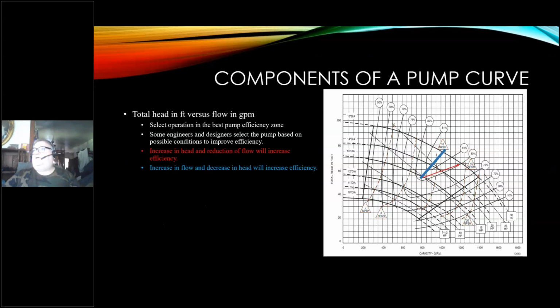All right, total head. Let's talk about how these interact. Total head in feet versus flow. Okay, this is the resistance. Select the operation of the best pump efficiency zone. So that blue line kind of tells us this is the straight line where we might get the best efficiency. Some engineers and designers select the pump based on the possible conditions. Again, the selection is made based on the design, but that's not necessarily what they're going to see in the field. So in some cases, they will select a pump to operate on one side or the other of this blue line, so that a change would either improve efficiency if I had a change in flow, or improve efficiency if I had a change in resistance. So it either moves one way or the other from this blue line.